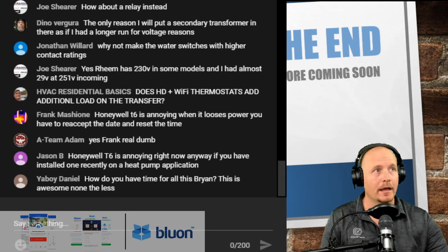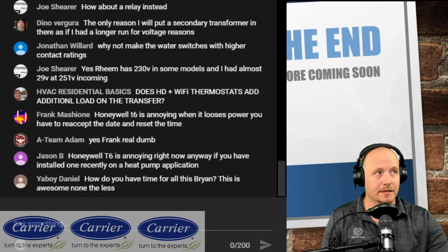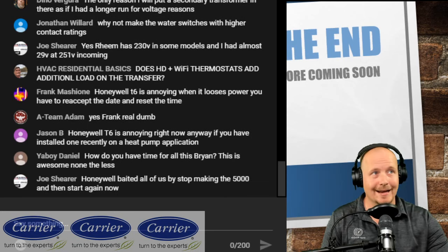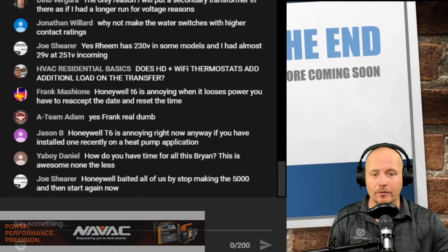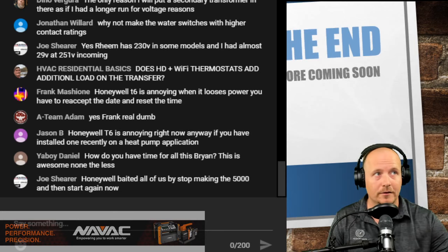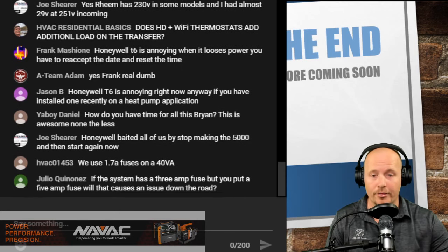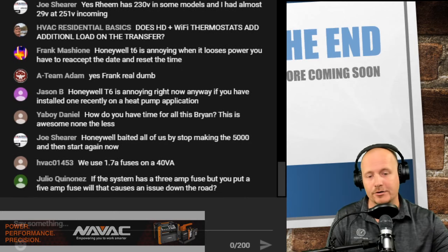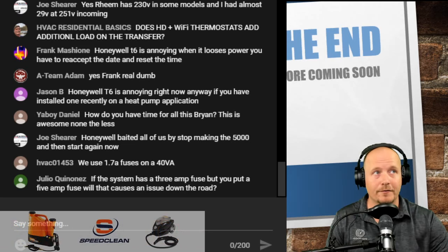That's all I'm saying. Joe says, yes, Rheem has 230 volts in some models, and I had almost 29 volts at 251 incoming. This is really key here, and this is kind of what I was trying to point out. In the equipment I work on, I don't see this regularly, but if you have a 230 volt primary transformer and you've got 250 volt incoming, you could have very high secondary voltage, and that could cause pretty significant problems.